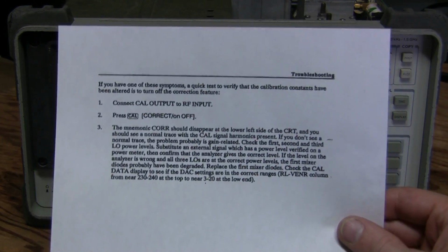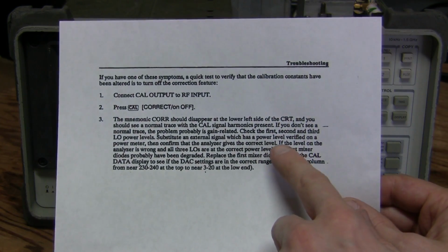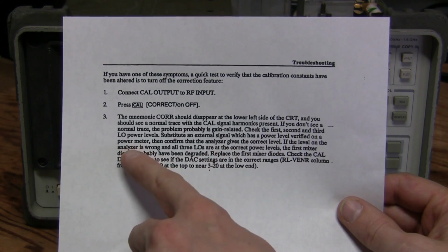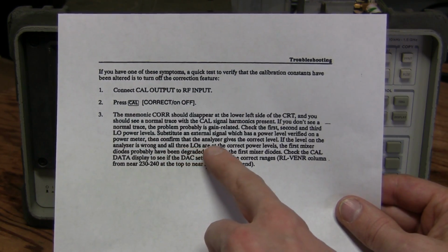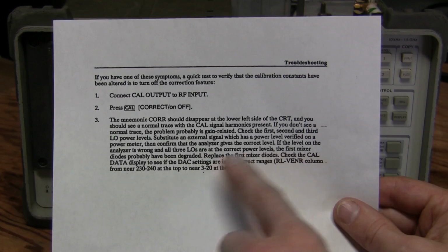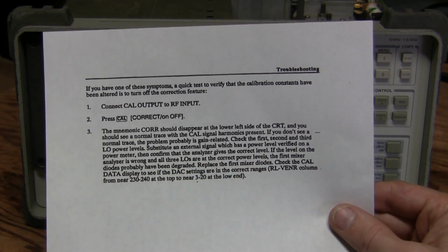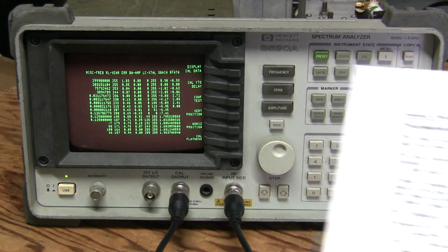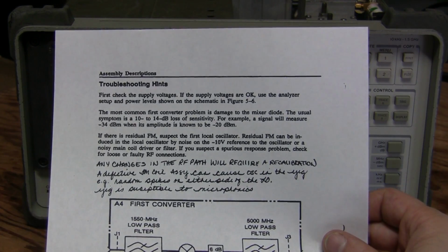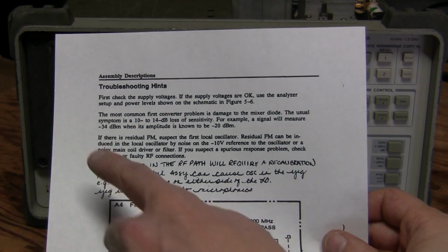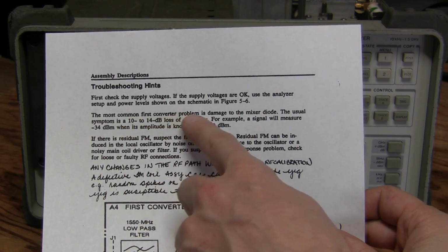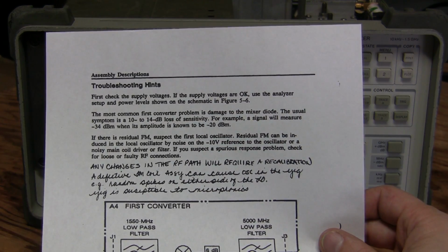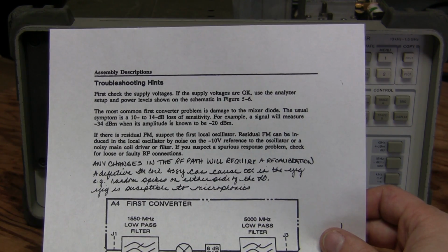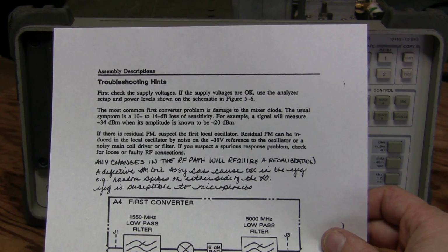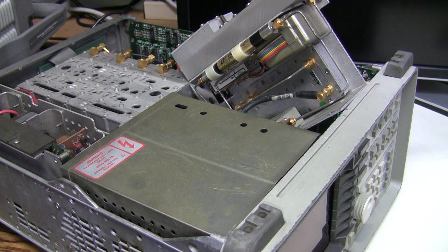And here, just above, they say if the level on the analyzer is wrong and all three LOs are fine, then the first mixer diodes probably have been degraded. And here, in the troubleshooting hints for the first converter, they say the most common first converter problem is damage to the mixer diode. The usual symptom is 10 to 14 dB loss of sensitivity. Let's check this first converter.